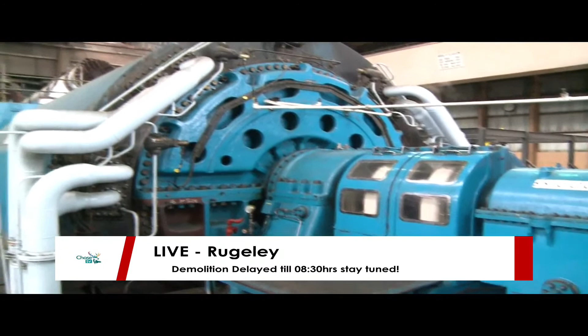Attached to this turbine is a generator, and the generator is just a big magnet rotating within a big set of copper coils. And if you rotate a magnet fast enough in a set of copper coils, electricity is made in the copper coils. But this is no ordinary generator. It needs to be cooled because electricity is made in such quantities the copper will get hot, and it's cooled by water. The rotor, the magnet, can weigh 60 or 70 tons. It's going round at 3,000 revs, and it too needs to be cooled. And we use hydrogen. I can think of no more difficult combination of materials than high voltage electricity, which you make, water to cool it, and hydrogen to keep the rotor cool.